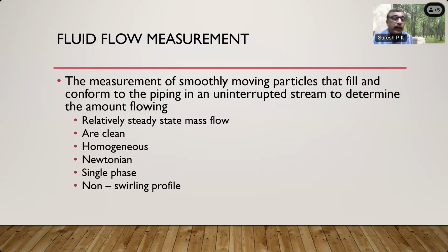Then we are assuming that the flow is single phase. Single phase means if it is liquid, it is purely liquid. If it is gas, it is purely gas. The gas and liquid are not combined, or sometimes gas comes and sometimes liquid comes. You can see the effect of gas coming through a liquid flow meter when the water is stopped in your home and then it starts coming, the air starts coming and the water meter runs mad, and you pay for the air, not for the water.